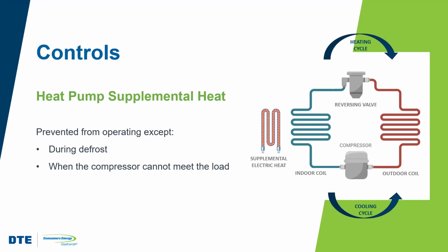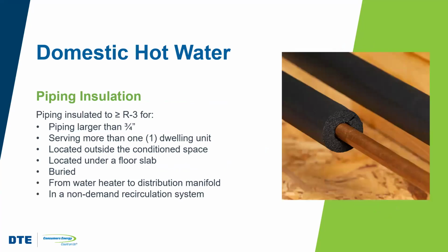Now, in the past, heat pump technology was not that effective here in cold climates like ours here in Michigan. But today, there are specially designed low temperature heat pumps that can efficiently provide heating in heat pump mode all the way down to about 5 degrees Fahrenheit. So we want to make sure that when we're applying heat pump technology, we're applying those low temperature heat pumps designed for our climate, and that they have a controller either at the thermostat or an integral control that only brings on that electric supplemental heat, which is far less efficient than heat pump heat. We want to make sure that we're only engaging that when it's absolutely necessary.